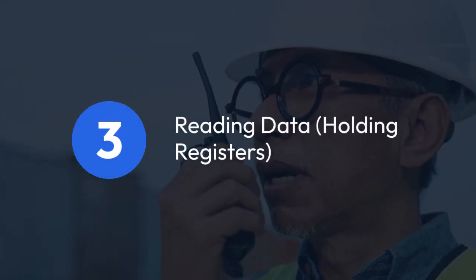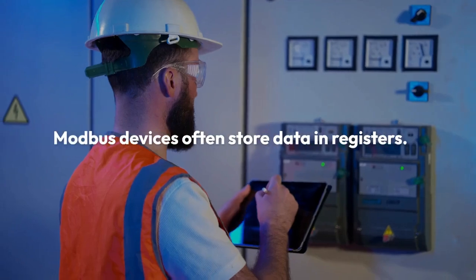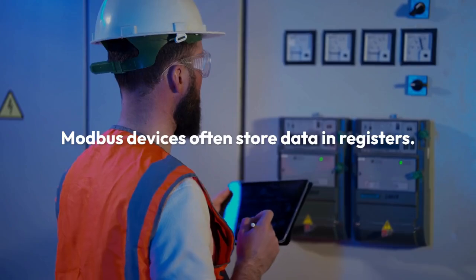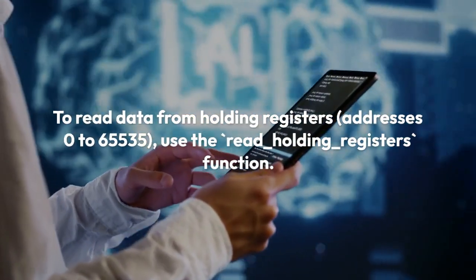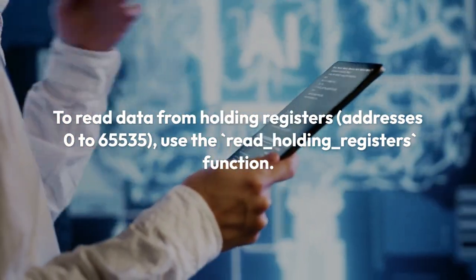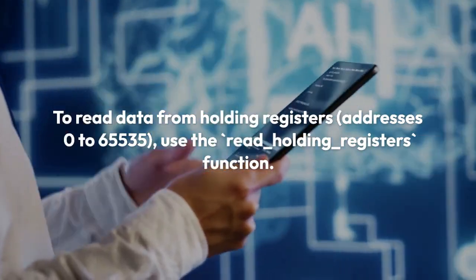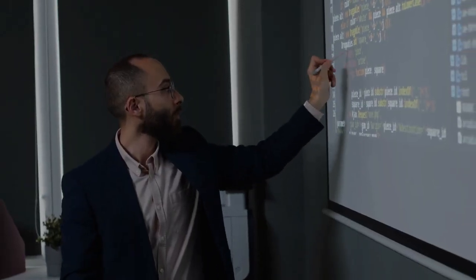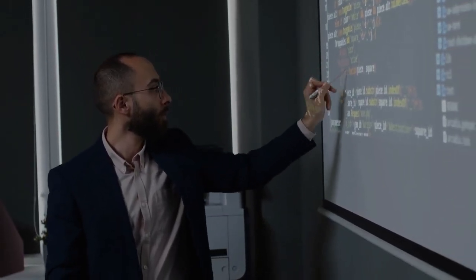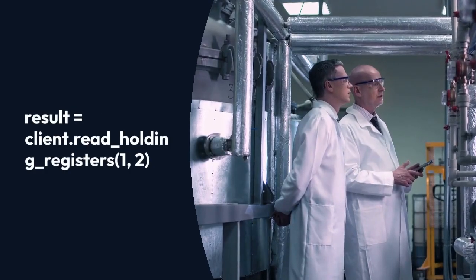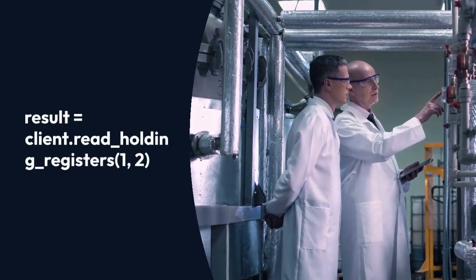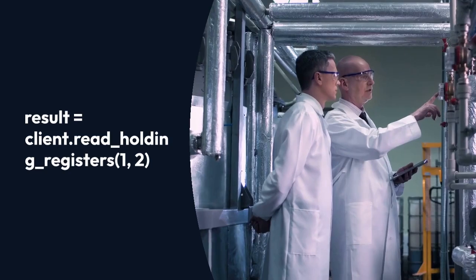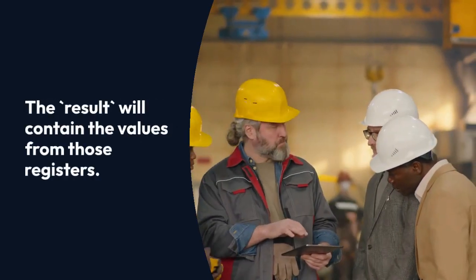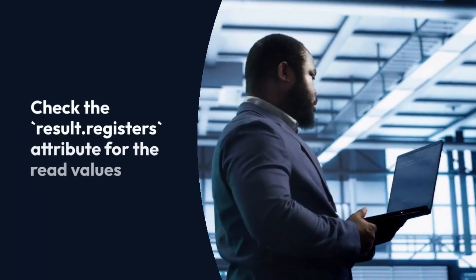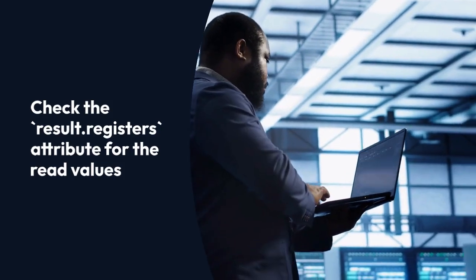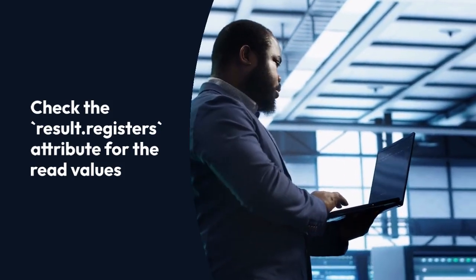3. Reading data, holding registers. Modbus devices often store data in registers. To read data from holding registers, addresses 0 to 65535, use the read_holding_registers function. This function takes two arguments: the starting address of the register and the number of registers to read. For example, result = client.read_holding_registers(1, 2) reads two registers starting from address 1. The result will contain the values from those registers. You'll need to check the result's registers attribute for the read values and handle potential exceptions, like connection errors.